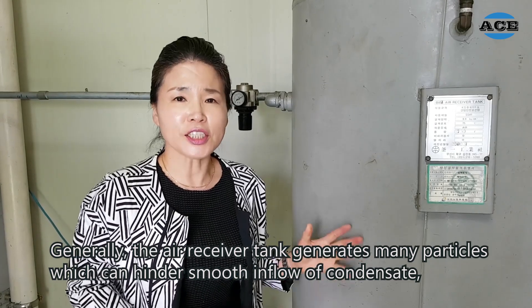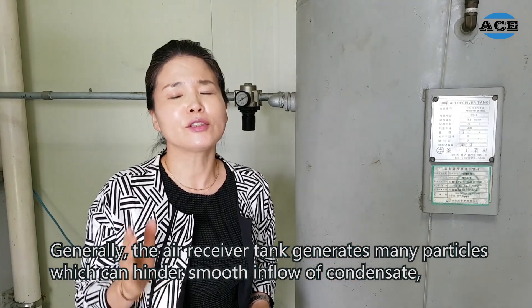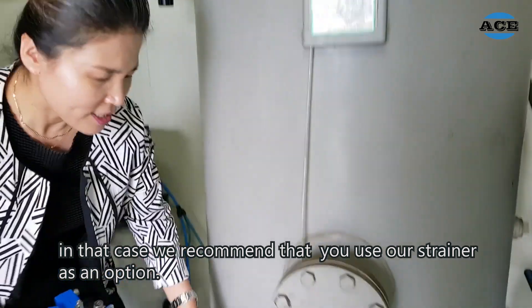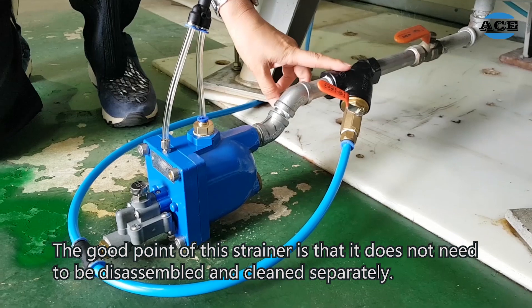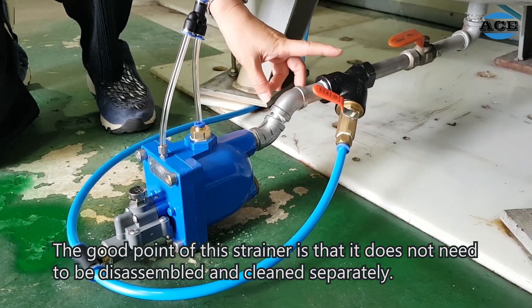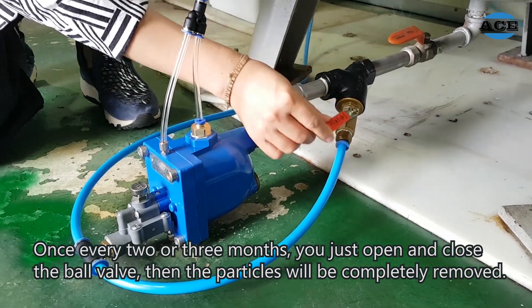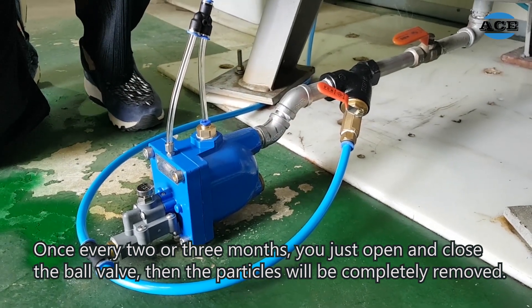Generally, the air receiver tank generates many particles which can hinder smooth inflow of condensate. In that case, we recommend using the strainer as an option. The good point of this strainer is it does not need to be disassembled and cleaned separately. Once every two or three months, you just open and close the valve. Then the particles will be completely removed.